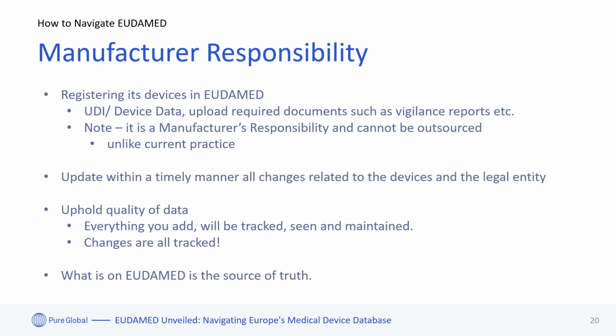It's the manufacturer's responsibility to register its devices, upload all required information, and ensure all data stays up to date in EUDAMED. Outsourcing this task is not allowed. It must be managed internally to ensure quality and traceability. Of course, you can have support from consultancy firms in guidance, right, and helping you set this up. But the final registration remains in the hands and the responsibility of the manufacturer.